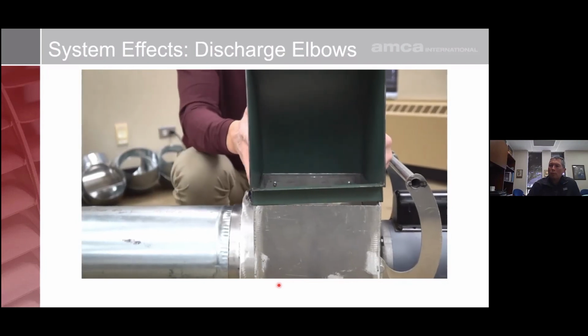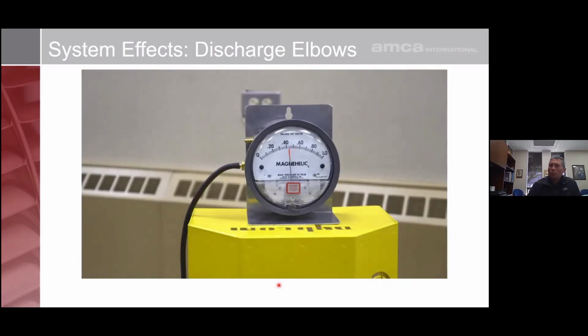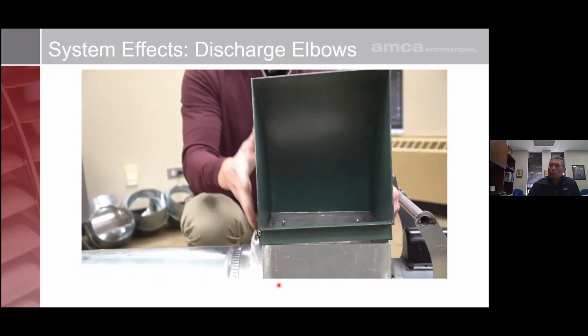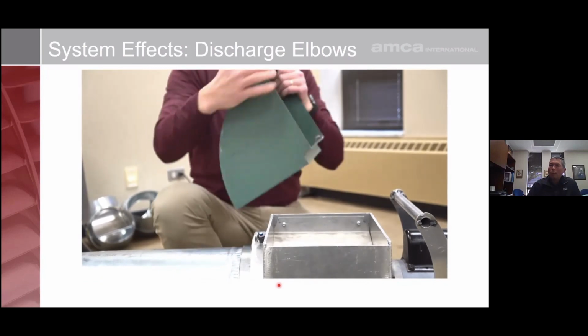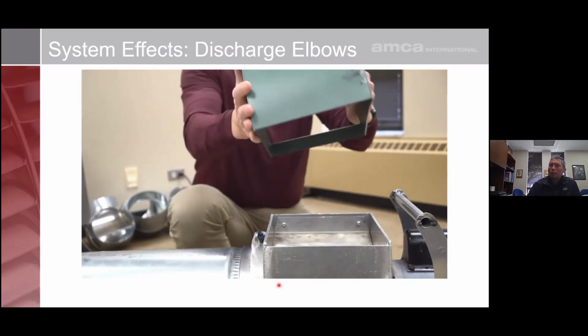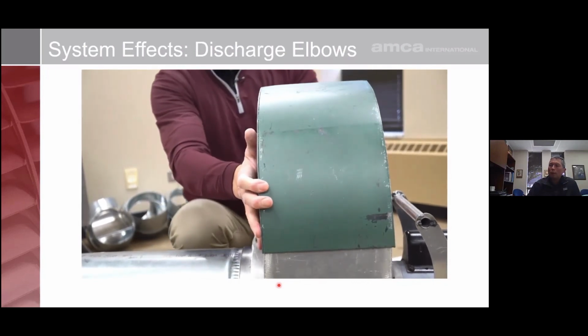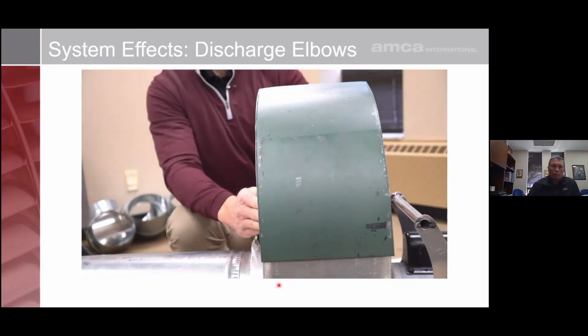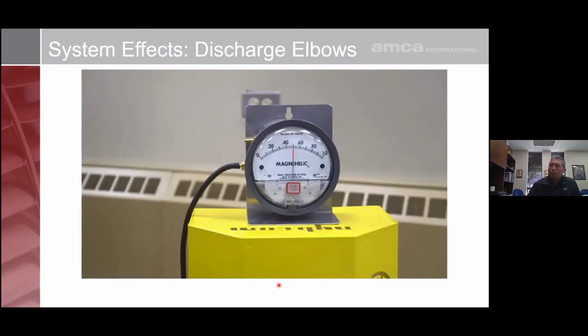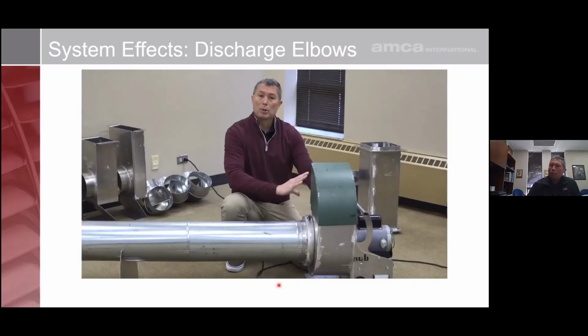So if I put the elbow on this way, notice the performance is decreased when you look at the magnehelic gauge. Now if I take that same 90 degree elbow, turn it 180 degrees, and now the outside follows the volute shape, you notice that there's very little change in performance when we look at the magnehelic gauge. Then we can put our straight run of ductwork here. It'll allow the velocity profile to even out, and we can get our static pressure regained with very little loss.